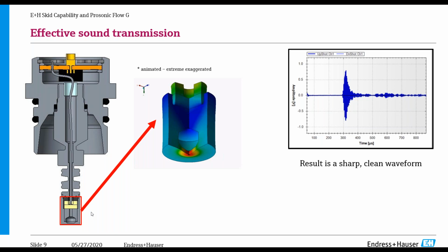That's what's going to generate the sound. And it's also a receiver. So you have a set of transducers in there. One is transmitting and the other one is receiving. So you're sending that signal upstream and downstream, so they reverse. And so with the piezo, what we want to do is use all that energy and, as efficiently as possible, transfer it into the gas so we get a nice clean signal.